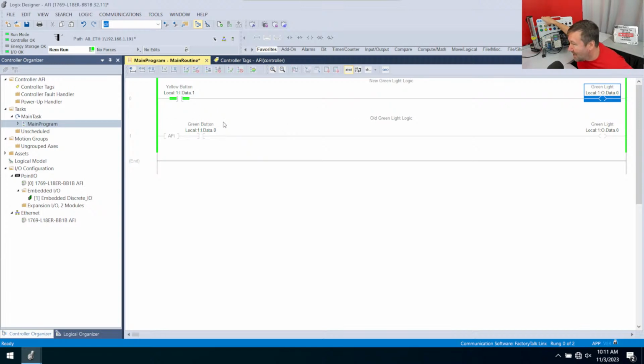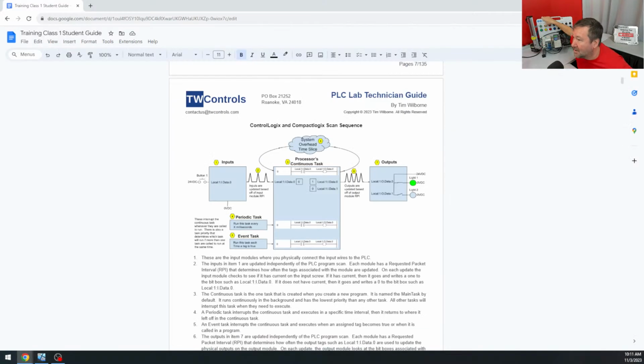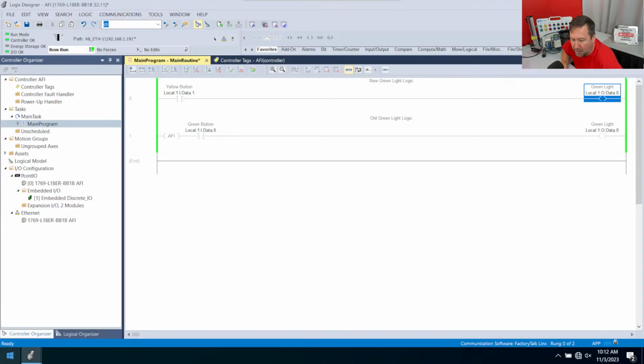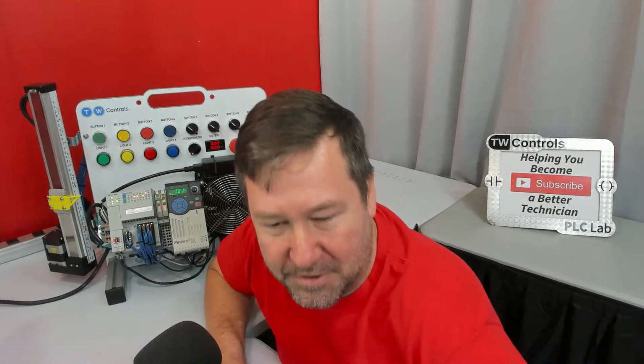Now here's where the continuous task, that little bit of overhead step, is coming in and causing us more erratic issues. If we go back and look here, we had this overhead, and I rarely even mention it because it's fairly insignificant on any large program, but right now we only have a 2-line program. This is where the PLC services communications and does a lot of things that we never even worry about. So we're going to try to slow this program down, and we're going to do it with a jump and label, just like we did in the last one, to actually disable the rung.